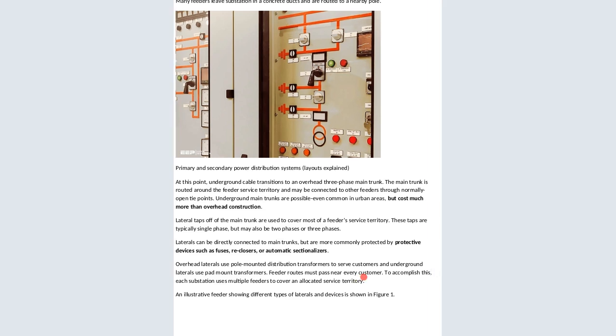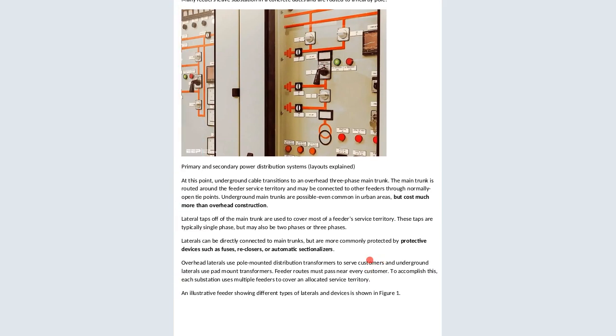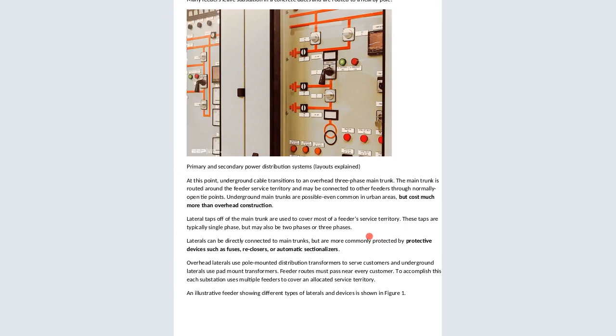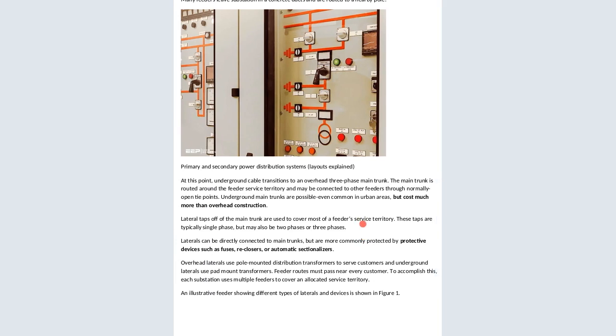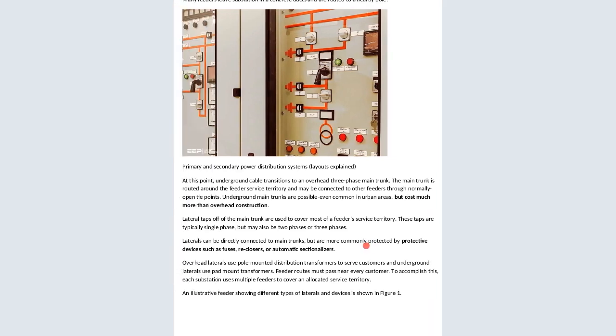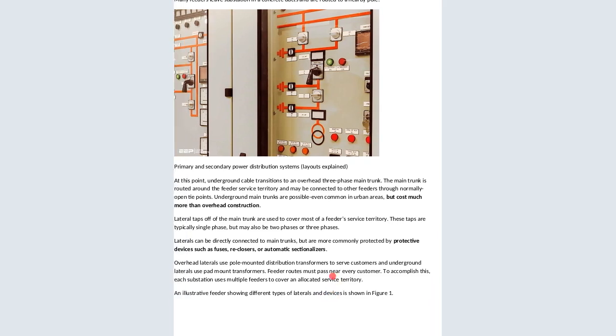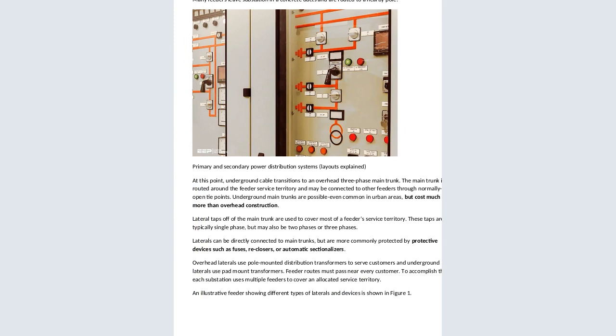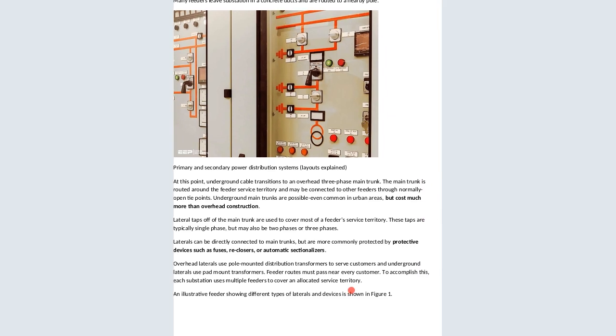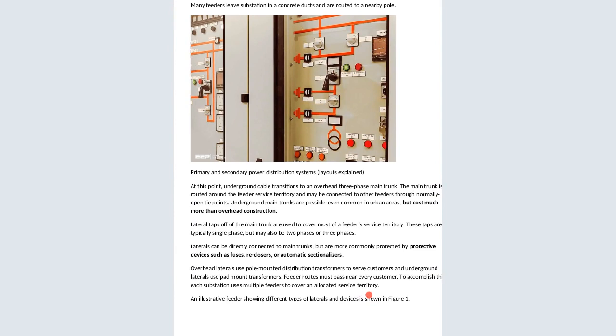The main trunk is routed around the feeder service territory and may be connected to other feeders through normally open tie points. Underground main trunks are possible, even common in urban areas, but cost much more than overhead construction. Lateral taps off of the main trunk are used to cover most of the feeder service territory. These taps are typically single phase, but may also be two-phase or three-phase. You normally see them in our connections. Laterals can be directly connected to main trunks, but are more commonly protected by protective devices such as fuses, re-closers, or automatic sectionalizers. Overhead laterals use pole-mounted distribution transformers to serve customers, and underground laterals use pad-mounted transformers and feeders.